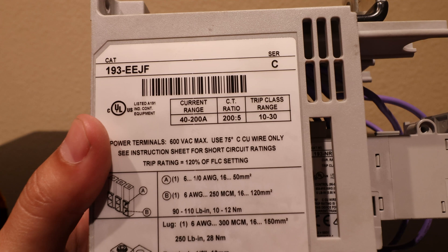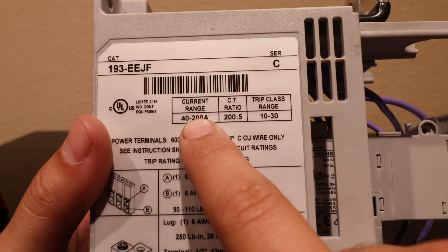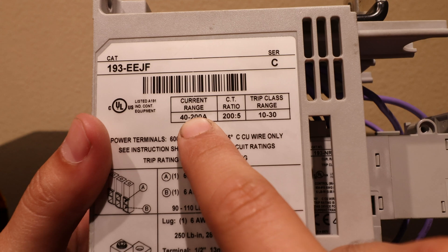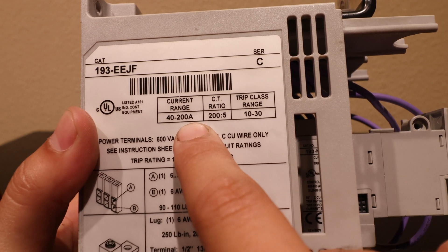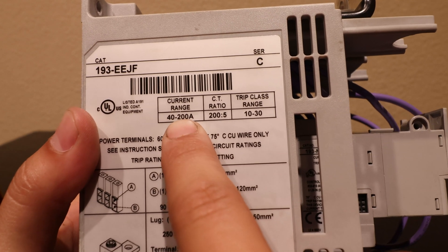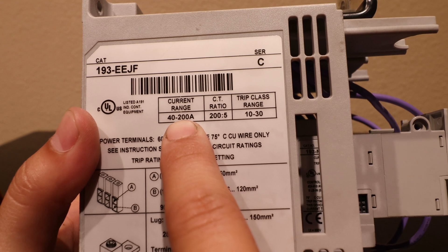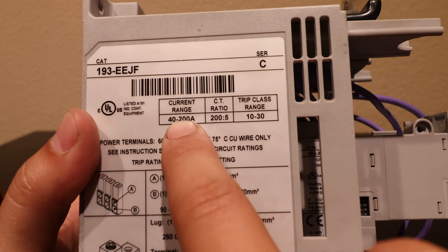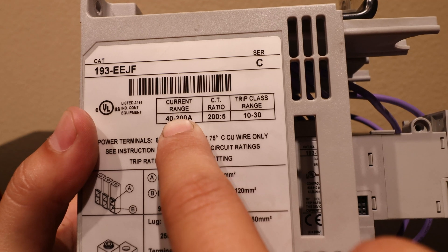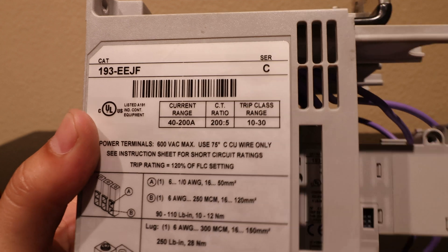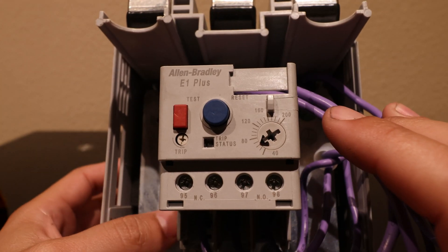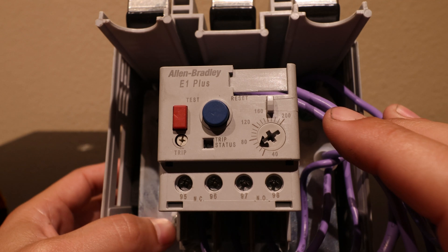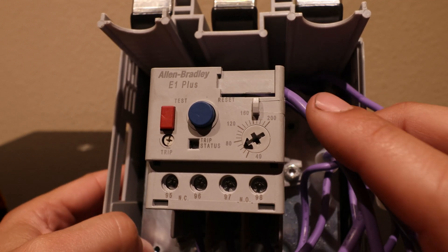All right let's check out the nomenclature on the side of this overload. The current range is the current range that it's protecting. This overload is protecting the main motor of an air compressor. If the air compressor is taking in maximum amount of air it can and making the highest pressure that it can, that is typically around the full load current that that motor is supposed to draw. If you decide that it's 180, then you will set it to 180 by the dial on the front.